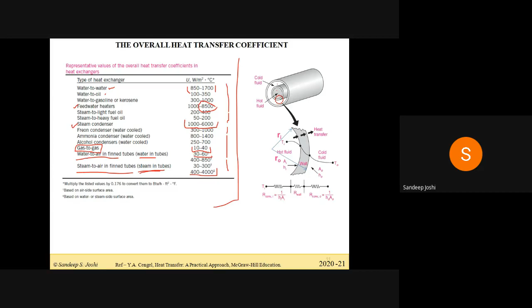But there are certain cases where you require the heat transfer coefficient to be more in order to achieve a higher heat transfer rate. For example, here you can see the feed water heaters, where the maximum is given, U, that is 8500. In some applications, like the most popular application in the power plant, the steam condenser, the overall heat transfer coefficient is 1000 to 6000. Again, you can consider the steam to air fin tube, that is steam inside the tube. In this case you can see 400 to 4000 is the value of the overall heat transfer coefficient. Okay, so these are the general values, which will give a general idea about the values of overall heat transfer coefficient in these tubular heat exchangers.